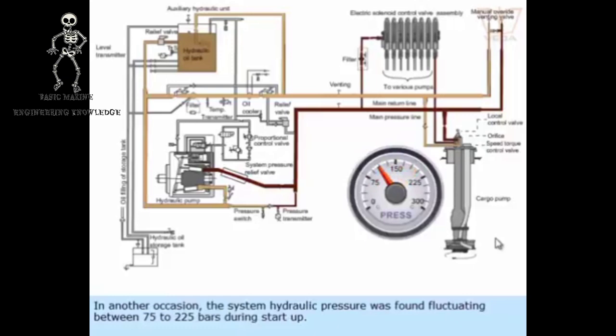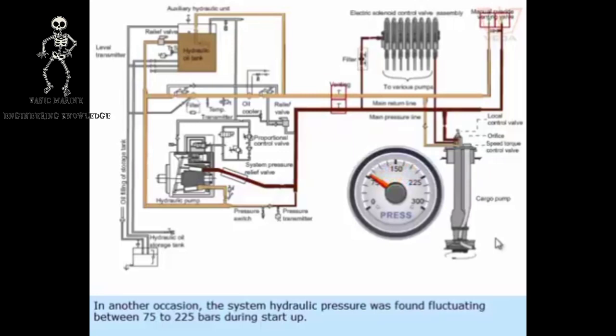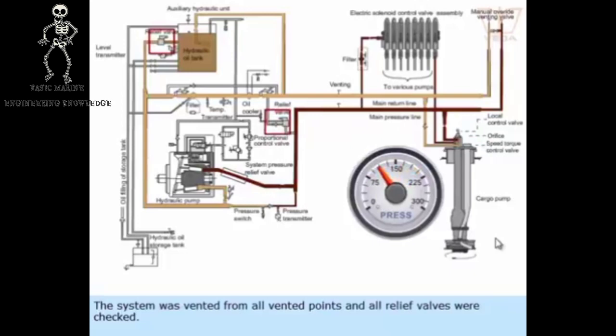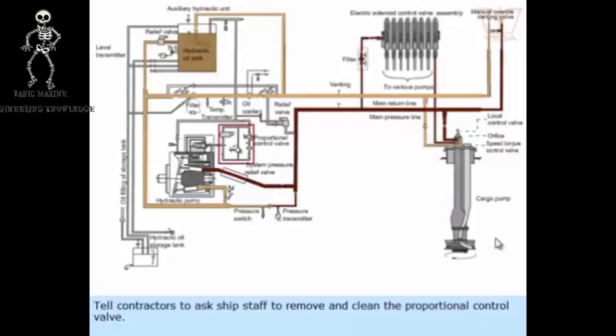In another occasion, the system hydraulic pressure was found fluctuating between 75 to 225 bars during startup. The system was vented from all vented points and all relief valves were checked. The problem could not be solved on board.